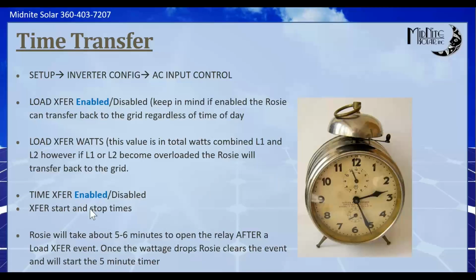And in time transfer, you would enable it, and then you have your transfer start and stop times, just like a clock, like an alarm clock. You set it hours and minutes, what time you want it to open the relay, and what time you want it to close the relay. Pretty straightforward on that. And the one thing I do want to point out is the 5 to 6 minutes, because this was also brought up. When you do a load transfer to the grid, once that load falls below the target, a timer starts for 5 minutes, and it can be up to 6 minutes depending on where you catch it in the cycle. So it'll be between 5 to 6 minutes, and then it will open the relay and disconnect from the grid.